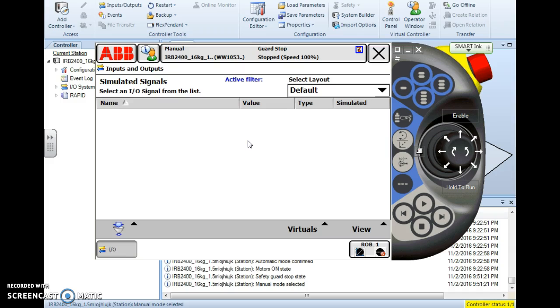So simulating an input may be something necessary to get the robot out of a tough or tight spot if you have a malfunction on your tool or on another device that the robot is working with. But just remember the simulation doesn't go away. When you reboot the controller the simulation will default to a state of 0. So you will have to manually remove that simulation at some point in time.